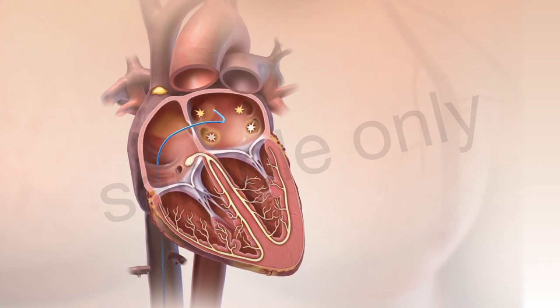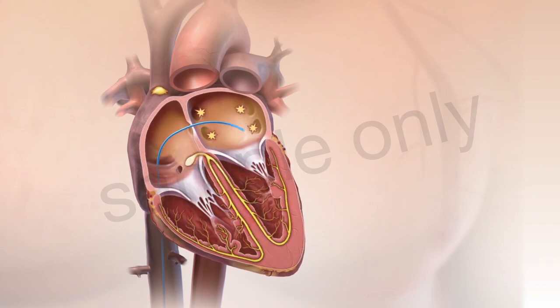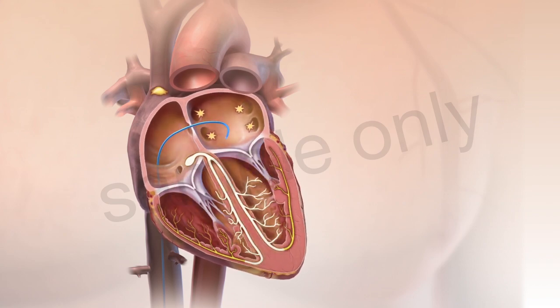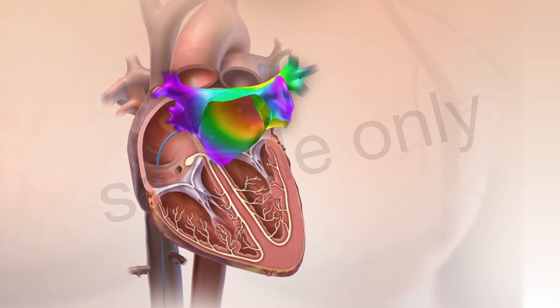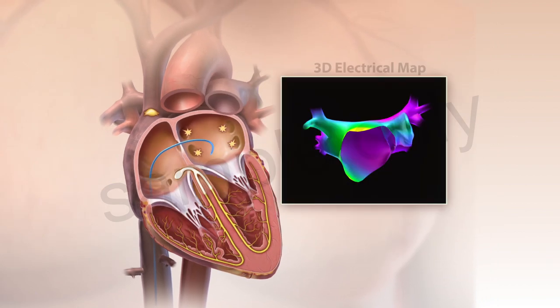This catheter can be used to sense electrical activity in the heart and map it on a 3D model of the heart's chambers.